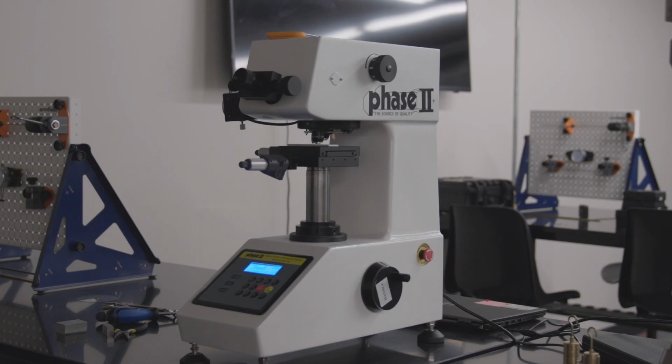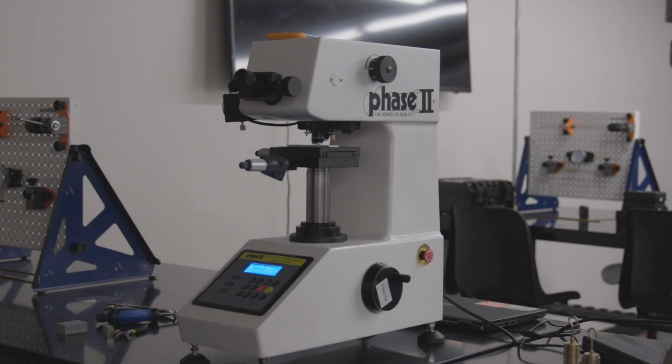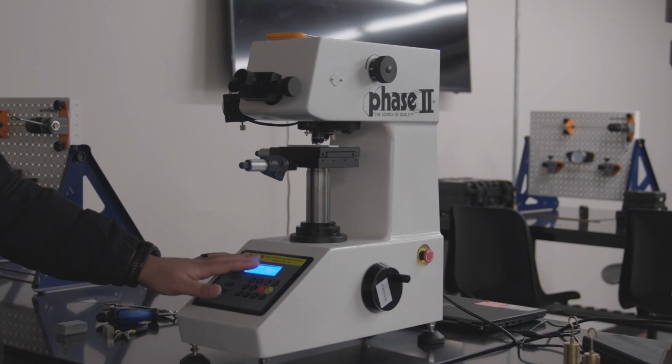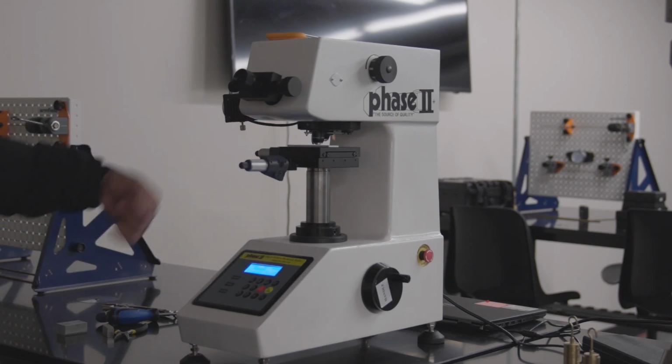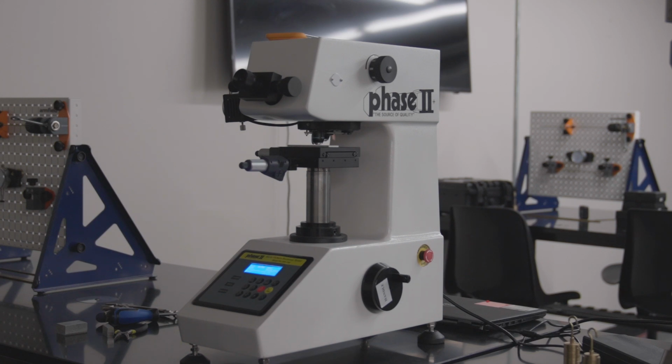As I mentioned earlier in the video, we have 2 different types of devices for the Vickers hardness test. The second one is the phase 2 micro Vickers hardness test. This is a bit more advanced, and you don't really need to change any of the settings that you see here. You want to just make sure that the turret is placed on the correct spot, and you have to just apply the load. You don't change the load or anything. Just move the levers and apply the load whenever you are ready.